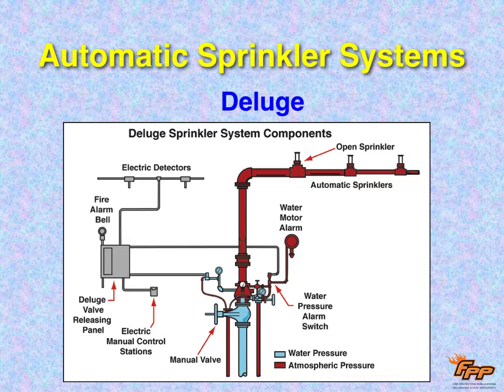That doesn't exist. What happens with this system is there's either smoke or heat detectors, and you see in your top left it says electric detectors. The detectors sense the heat or the smoke. They send a message to the fire alarm control panel. The fire alarm goes off, and the message goes to the sprinkler system, where there's an automatic valve that is going to get opened automatically. There's no air pressure in there. The water's just going to shoot into the pipe, and it's going to come out every single sprinkler head. Now, remember how that works, because pre-act is kind of similar.